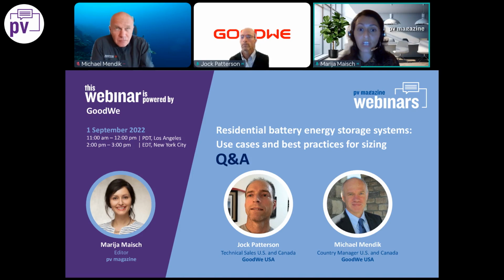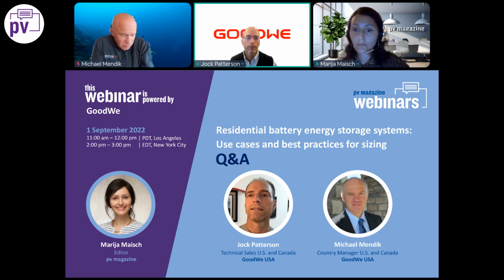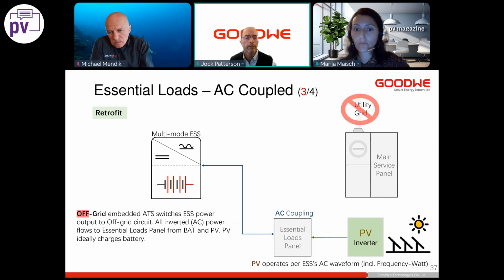This question refers to slide 39. It asks, are microinverters capable of ramping down by certain amounts, or do they just shut off with the frequency change sent out? Of course, it depends on the microinverter, but today's microinverters should act like PV inverters and have a frequency-watt response built into them. That said, anybody installing a backup system should always check that the existing PV inverter, microinverter or not, truly has that frequency-watt functionality.